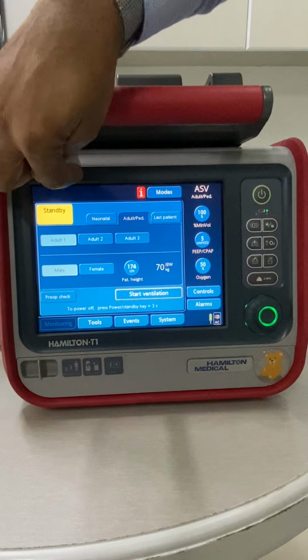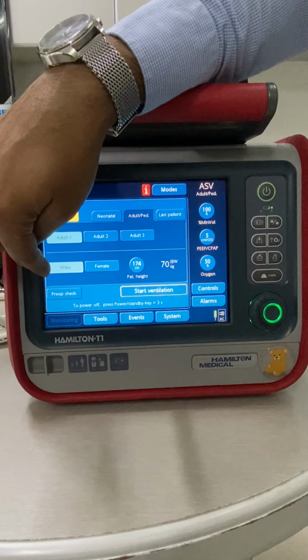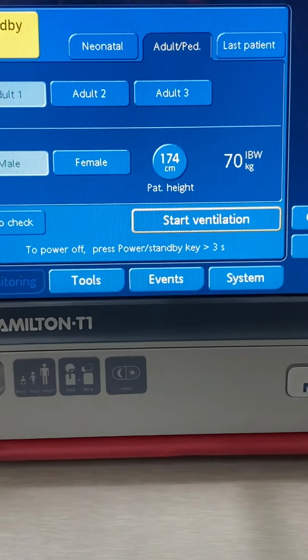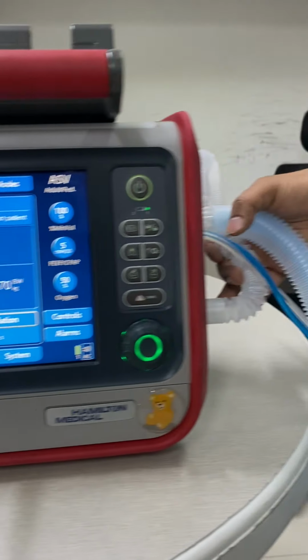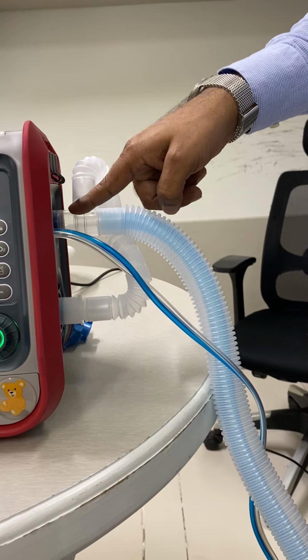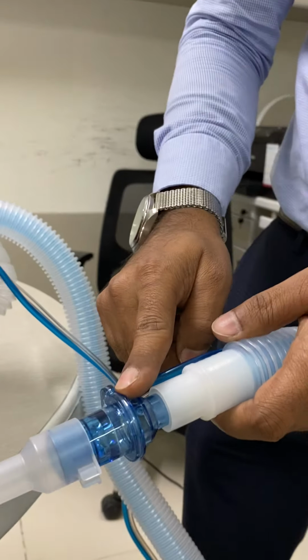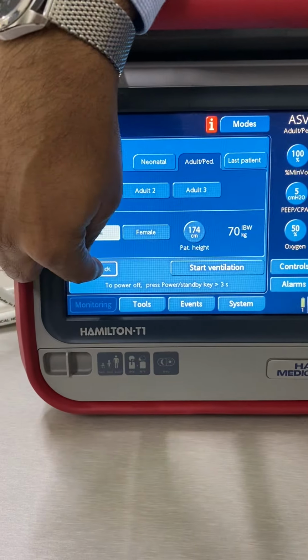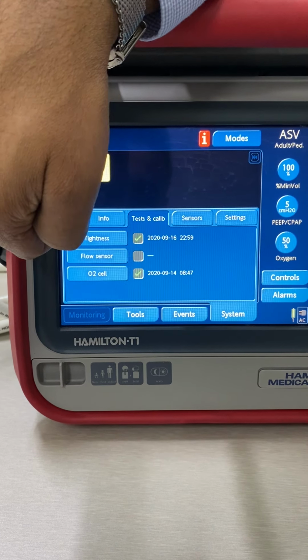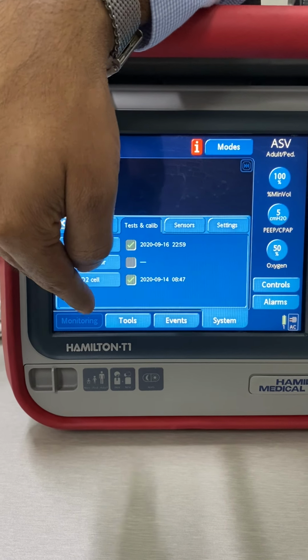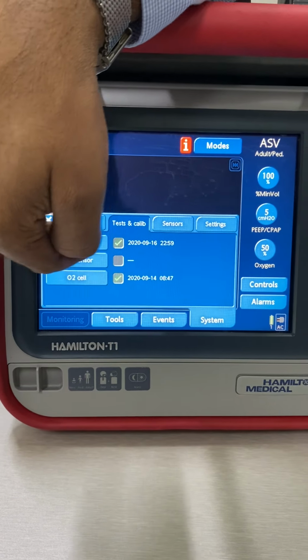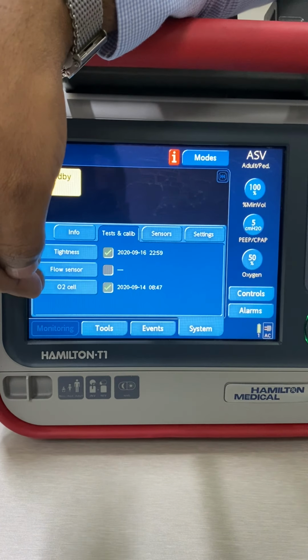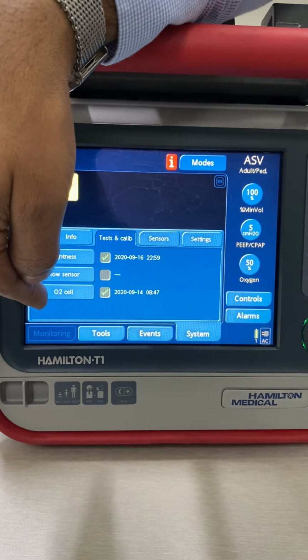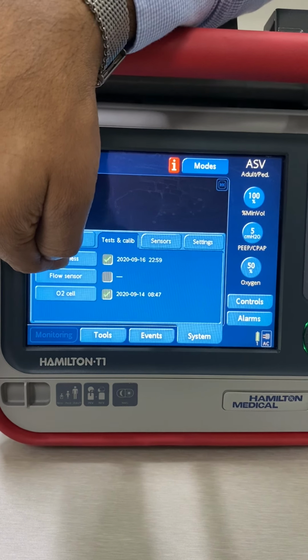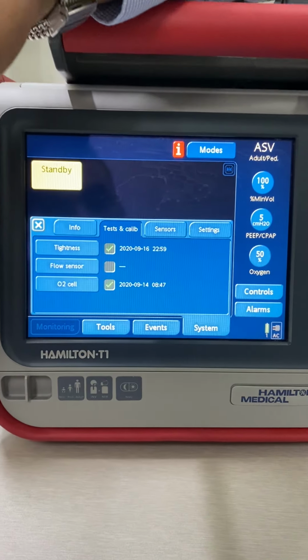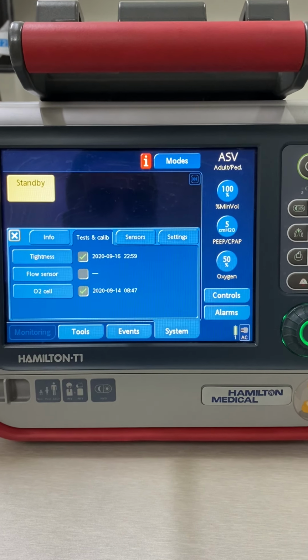Then first of all you need to do the preparation of the ventilator. Make sure that you have connected the tubing and flow sensor accordingly, the inspiratory, expiratory and the flow sensor, connected over here. Then go to the pre-op checkup. We have the tightness, flow sensor and O2 cell checks. The O2 cell is for monitoring the FiO2 delivered to the patient. You don't need to calibrate the O2 cell all the time, you just have to do the tightness and flow sensor checks whenever you are changing to a new tubing or a new patient.